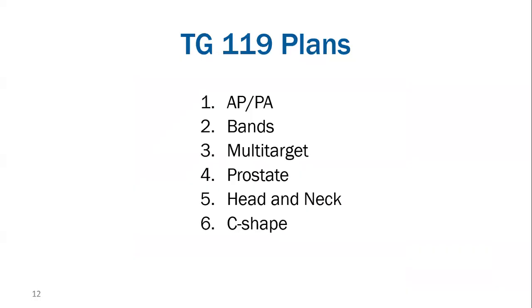So when they talk about TG119, they talk about six specific plans of sort of increasing levels of complexity that allow you to characterize how good your system is. And when we talk about how good your system is, right, the accuracy of your dose calculation in your treatment planning system will depend on your MLC model, right? So the various parameters, and this depends again on which vendor you use, whether it's Varian or Elekta or another TPS, how they actually create the model, but basically just the physical parameters of the MLC leaves you need to model so that you can actually accurately calculate dose.